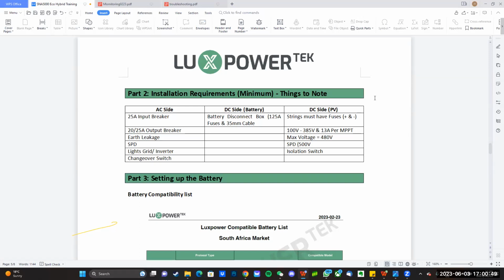From the DC battery side, you need a battery disconnect box, with a minimum requirement of 125 amp fuses and 35 millimeter cables. From your DC side of the PV, both your positive and negative strings must have fuses, rated 100 to 385 volts and 13 amps per MPPT.